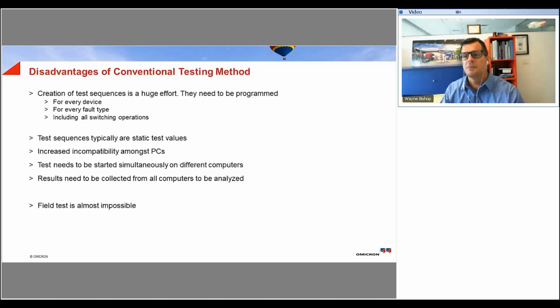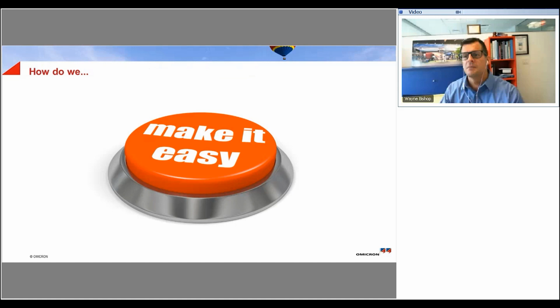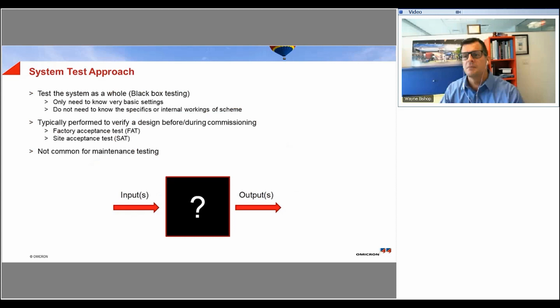So now we must ask the question, how can we make this easier for ourselves, right? Is there a button that we can press, like the old Staples commercial, I want to make it easy? For this, I'm going to propose the idea of a system testing approach, where we approach testing the DA scheme or the FLISR scheme as a black box, where we only have to know very basic settings of the system, of the specific reclosers, and we don't need to know the internal workings so much of the scheme. So what we're doing is basically applying some inputs and some stimulus to the system, and we're seeing how it reacts. This can typically only be performed during acceptance testing and commissioning, and it's not very common for maintenance testing.